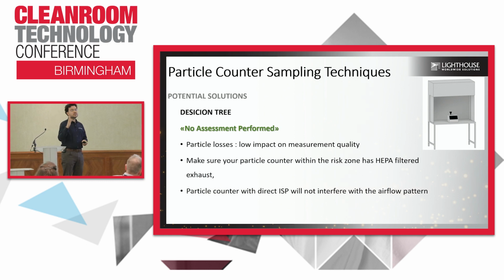Remember, the decision tree takes us into 3 different steps. One of them was no assessment performed, but we still have an impact of particle losses on our system design. And make sure your particle counter is within the risk zone, because you are going to put your particle counter directly into the critical area. In this case, we want to make sure that you have a HEPA filter exhaust, which means your particle counter is not contaminating your environment. And also, the particle counter with the isokinetic probe will not interfere with the airflow pattern, which means you're not putting it under the glove area or over the critical location. So you have to pick the right place within a certain distance.